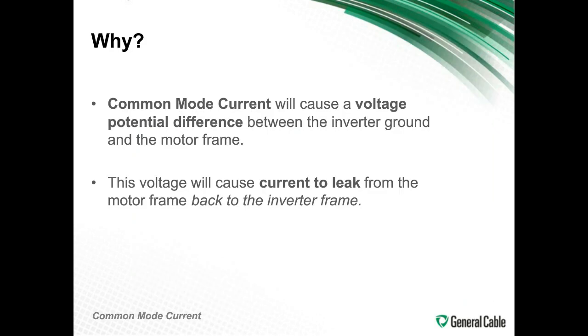So the common mode current will cause that voltage potential difference between that ground and the motor frame, and that is from the impedance mismatch between the cable and the drive. And when you have the drive cable attached to the drive and this high frequency pulse wave modulation waveform goes through there, if the cable doesn't account for that, it will definitely cause issues. And there's a leakage of current that the voltage causes from the motor frame back to the inverter frame, and it all gets into the system and causes harmonics that are really unnecessary and unwanted. This is current that does not do anything but cause problems.